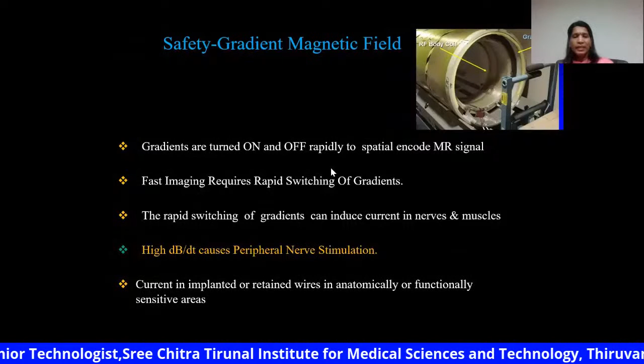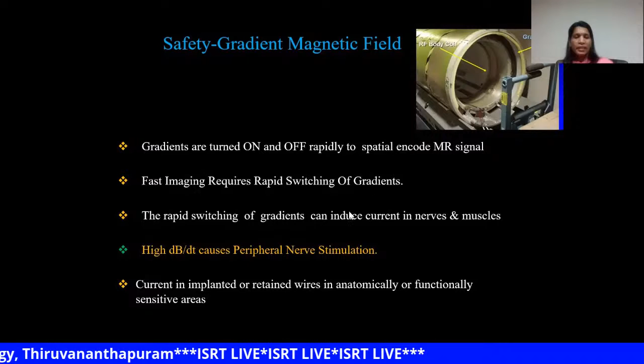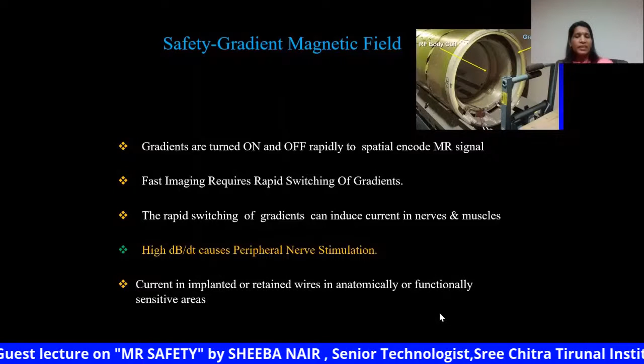So coming to the gradients, as I told you, in MR imaging you have to switch the gradients at a faster rate. Even fast imaging requires rapid switching of the gradients. When gradients are switched at a rapid rate, any conductive material there can have electric current induced in it. If these wires are in an anatomically or functionally sensitive area, it can produce hazards. Also, the higher switching of the gradient produces electrical polarization, and it can cause a false release of neurotransmitter at the axonal terminal, which results in peripheral nerve stimulation. Sometimes peripheral nerve stimulation can be very painful.